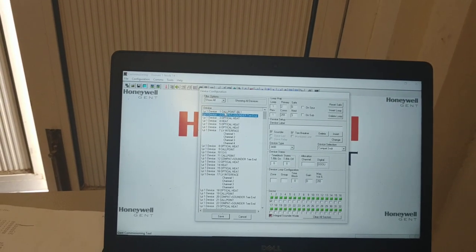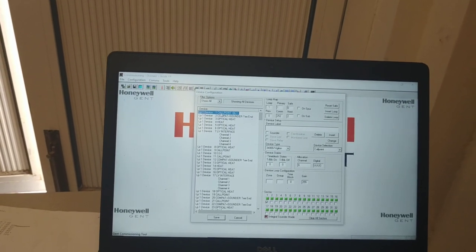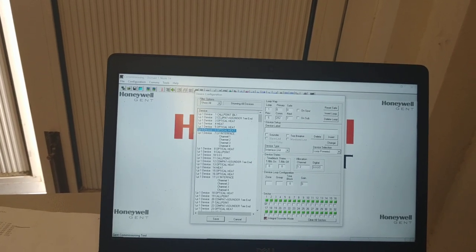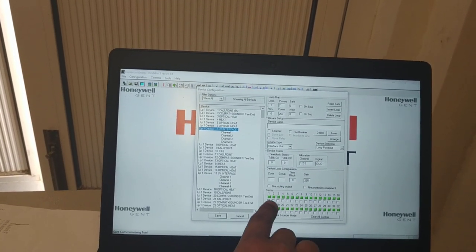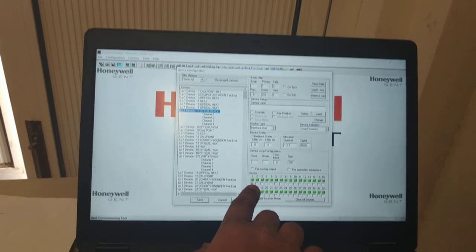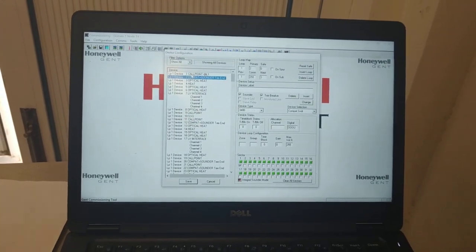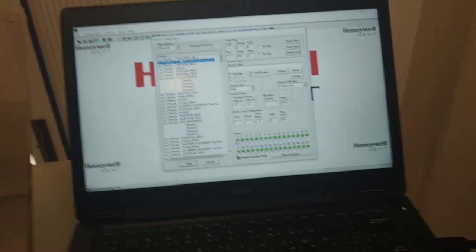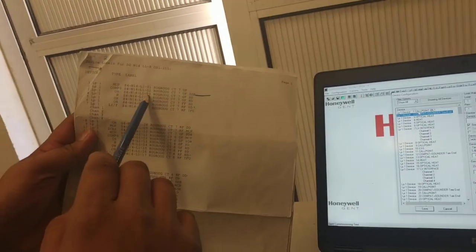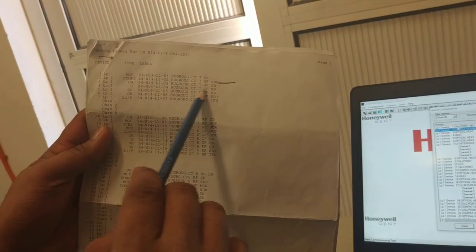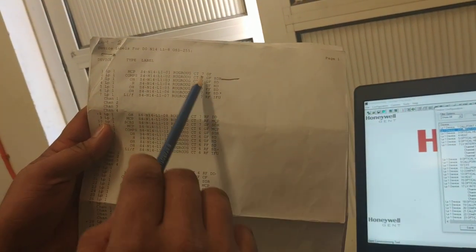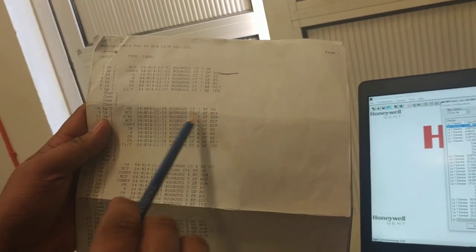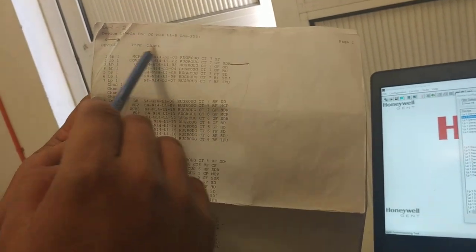Loop 1 now has no label. Loop 1 and Loop 2 — Loop 1 is no labels, and also the sectoring is all Sector 1. But as per our existing backup, Loop 1 should have different areas. That means we need to reprogram this.